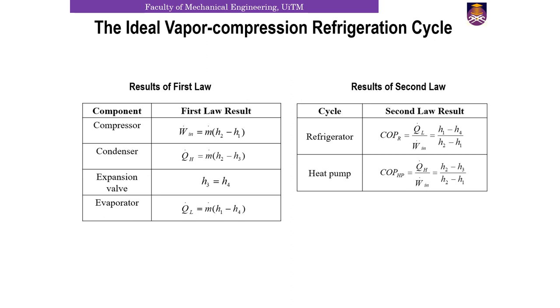Now, these are some of the formulas you can use. Based on our first law results for the compressor, the work in, based on the mass flow rate, is given by mass flow rate times the difference of enthalpy between points 2 and 1. In the condenser, QH is given by mass flow rate times the difference of enthalpies between points 2 and 3. At the expansion valve, we assume enthalpy at point 3 is almost similar to enthalpy at point 4. And for the evaporator, QL equals mass flow rate times H1 minus H4.